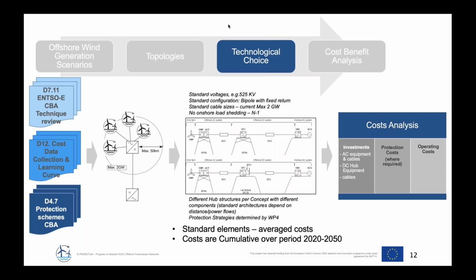We standardized on 2 gigawatt maximum cables based on onshore load shedding constraints, and these were lower for the UK, Ireland, and Denmark. However, if onshore constraints were relaxed, the size of the cable would need to change. The size of the cable has a large impact on total infrastructure costs. Therefore, if we would go to 4 gigawatts, this could lead to up to 40% in capex savings. However, we would need to find some way to land that power.